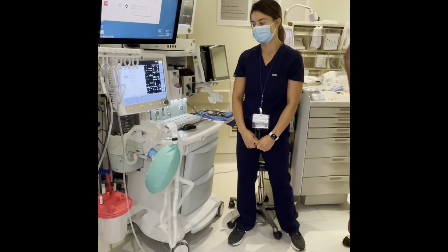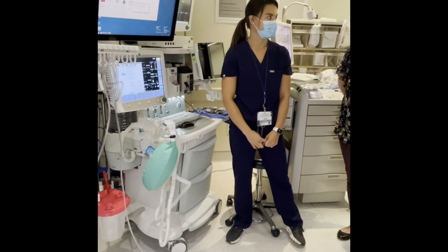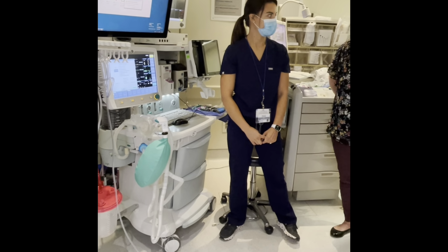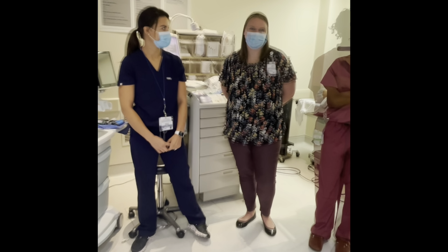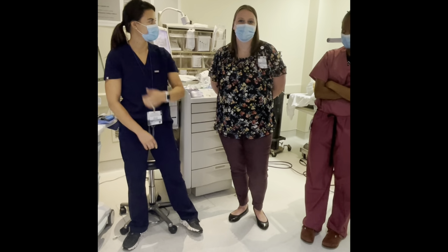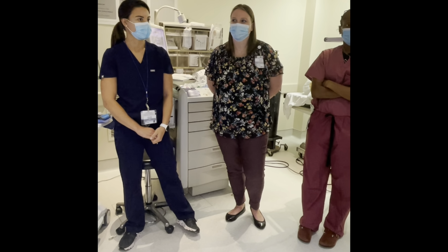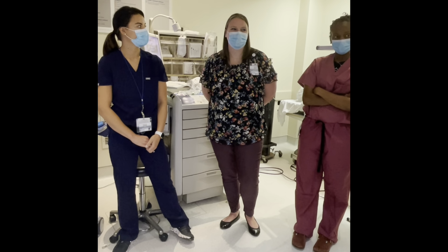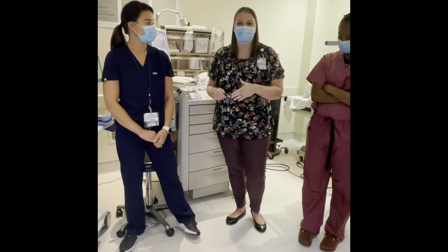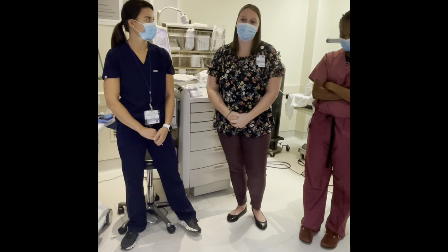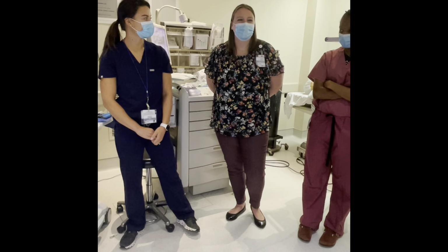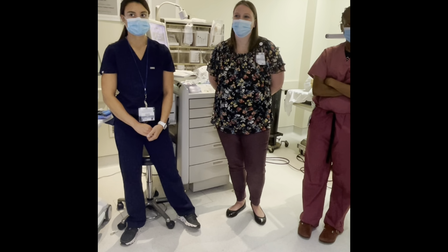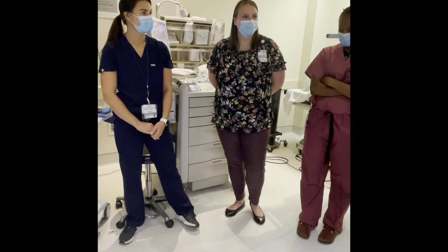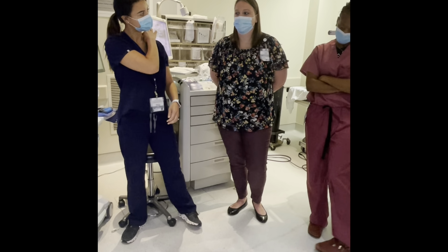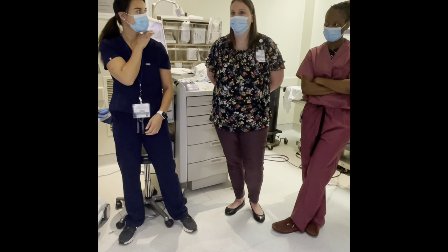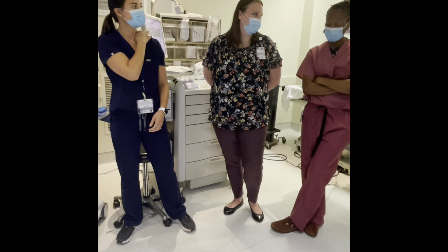You've touched it. So, the anesthesia machine. 3 pressure systems on the machine, right? I'll let Lauren do. Does anyone remember what the 3 pressure systems are? High pressure system, where does that start? Anyone remember? E-cylinders, yep, to the pressure gauge, yep. And then there's a pressure regulator as well that downgrades that pressure and gets it into the intermediate system. Does anyone remember what's included in the intermediate system? So that's gonna go, flow meters, yeah, are gonna be low. So intermediate is gonna be from that pressure regulator all the way to the flow meter valves.